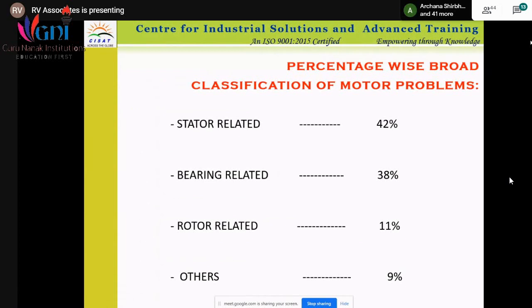This is the analysis that there are stator related faults around 42%. Another big chunk is bearing related problems, around 38% of faults. Then there are some rotor related faults and other normal faults, which lead to the remaining 9%. So there can be a terminal failure, an insulation failure, or maybe a hinge failure or a base failure. These all come under the others category.